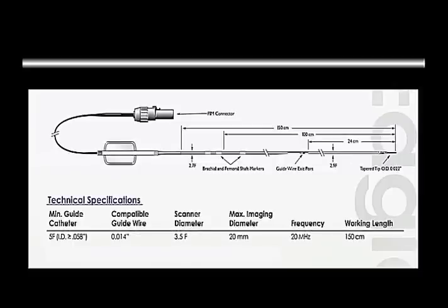Here's a device. There are two primary companies in North America. I'm not going to mention either one of them. You can see on this particular catheter, the far right, this area right here is where the guide wire enters and comes out here. And the rest of the catheter just follows along adjacent to the guide wire. The difference between the two is that one has its guide exit port only about a centimeter from the tip, and it's really not enough of a wire inside the lumen of the probe in order to give you good control.